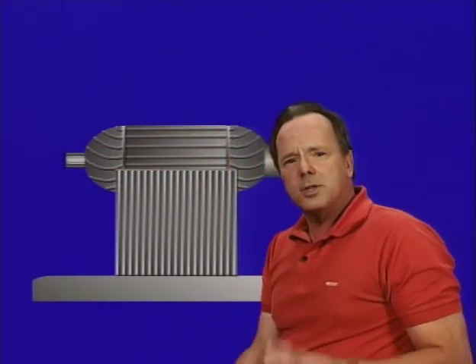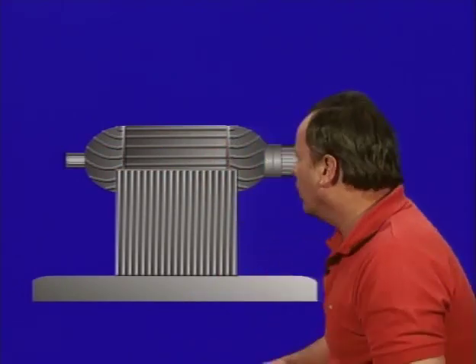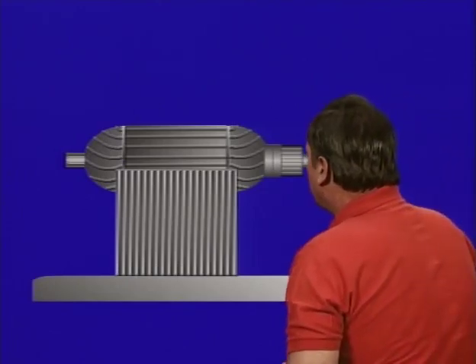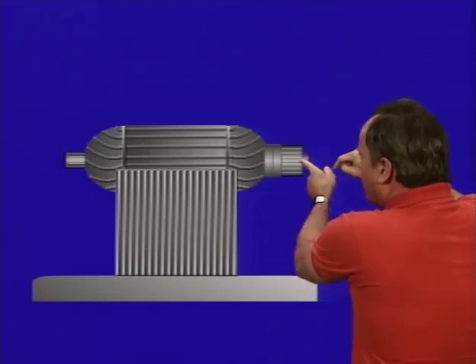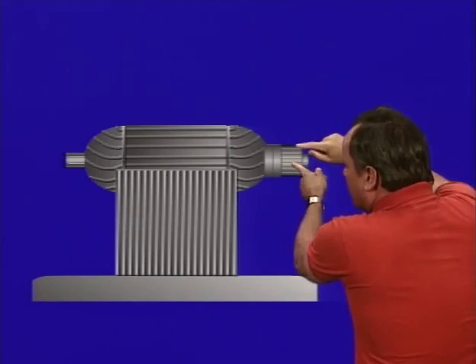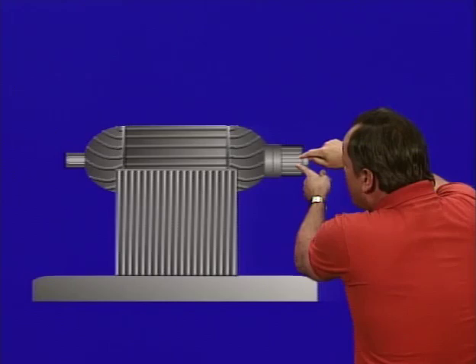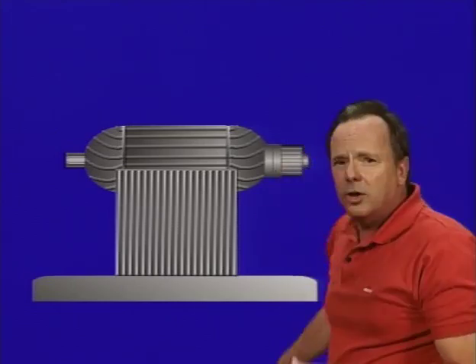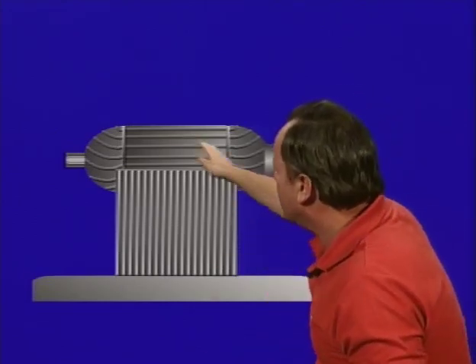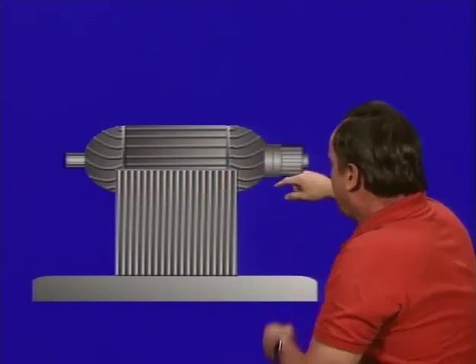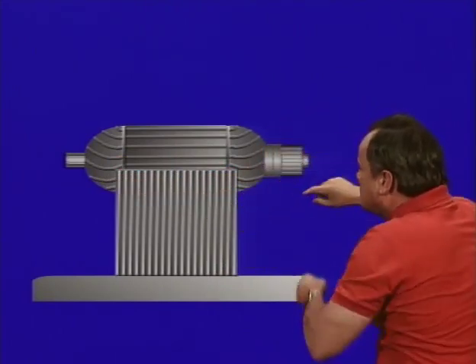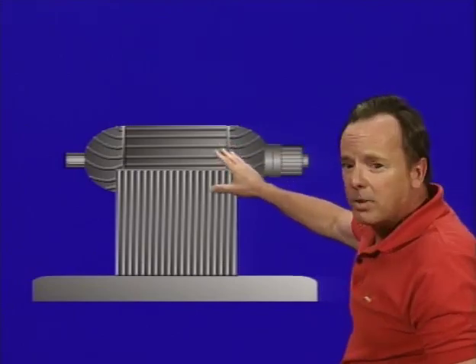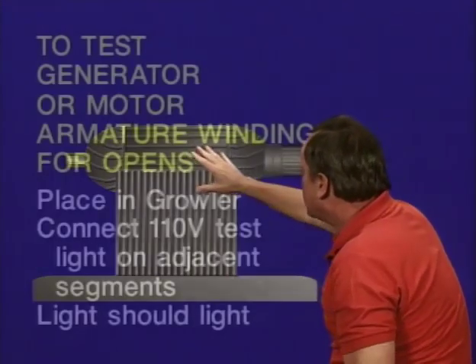And you can test to see if current is flowing where you want it to flow by using a 110 volt light with a couple probes on it. You put a probe on one segment and then put a probe on an adjacent segment. And if the windings do not have opens in them, then the light will light. Now, you don't want the segments to have opens in them. The windings should be continuous. So by checking adjacent segments, you can see if the light lights, and if it does, you know it's working properly.